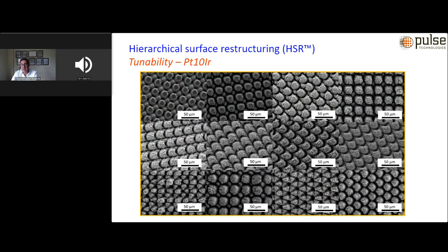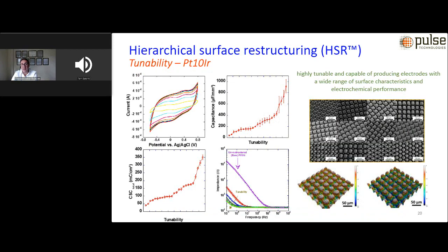I talked about tunability. As mentioned earlier, our technology has introduced a novel method for hierarchical surface restructuring of electrode surfaces using femtosecond laser, and the process promotes tunability and controllability of the electrochemical performance and characteristics of electrodes for various neural interfacing applications. There are a number of ways that we could tune and engineer the surface of the electrode in order to create topographies and surface structures that vary from one to another, and that way we could tune and design the kind of performance that you are interested in for your devices, and that's really incredibly unique in our opinion.